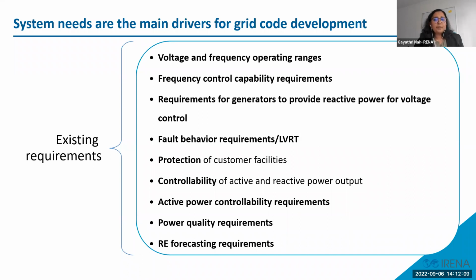In the case of fault behavior, it is basically to ensure predictable system behavior and to be resilient to grid faults. Protection is usually mentioned as the responsibility of the grid operator or of the project owner to see that the VRE power plants are protected and also to ensure that they are not overprotected in some instances. Then VRE systems that have been connected to the transmission network have to ensure that they are SCADA enabled and have SCADA enabled active and reactive power connection to the power system operator so that they can be remotely controlled and monitored.